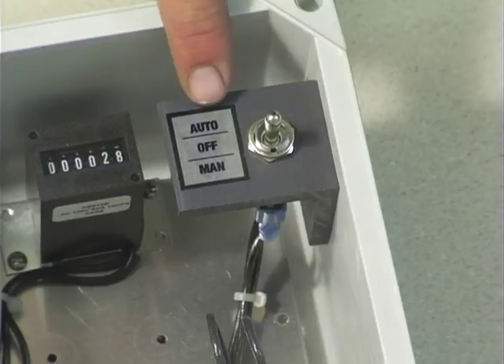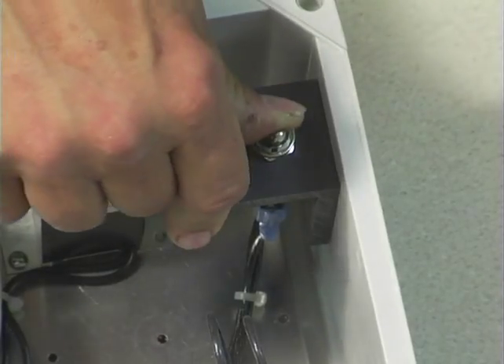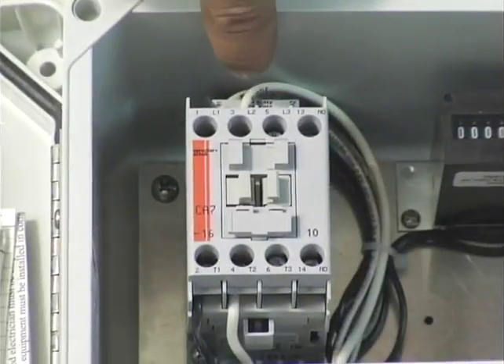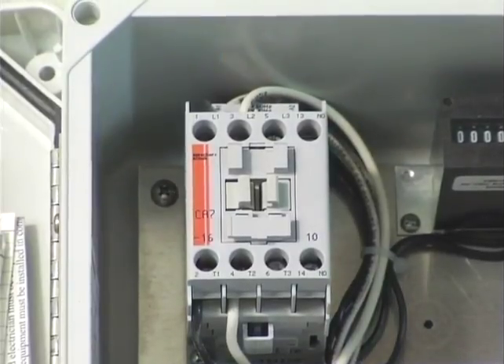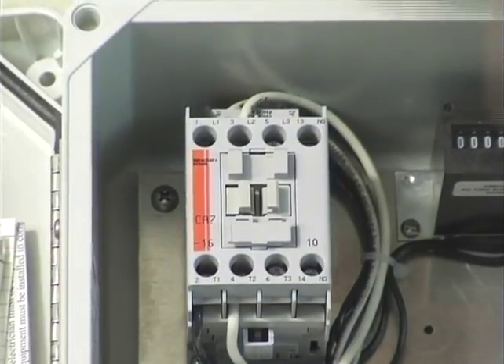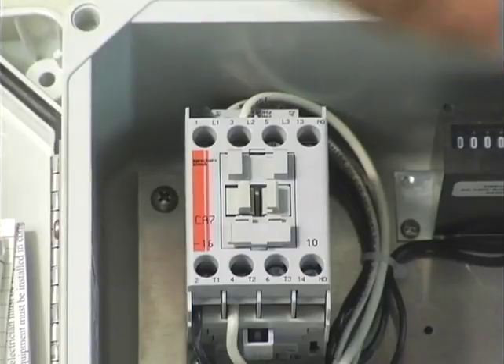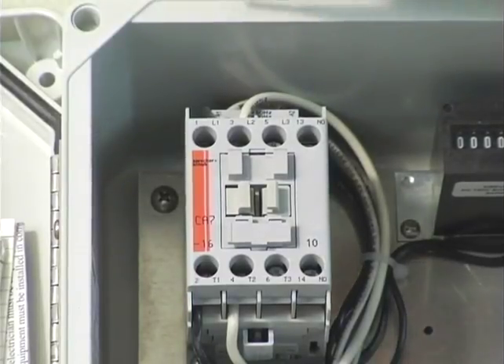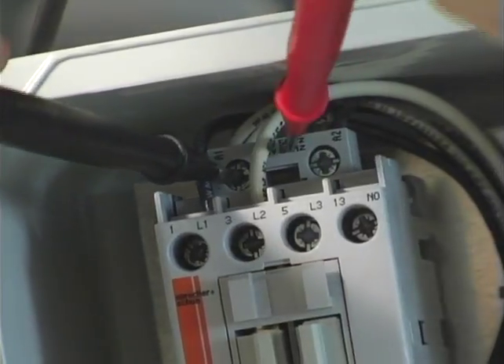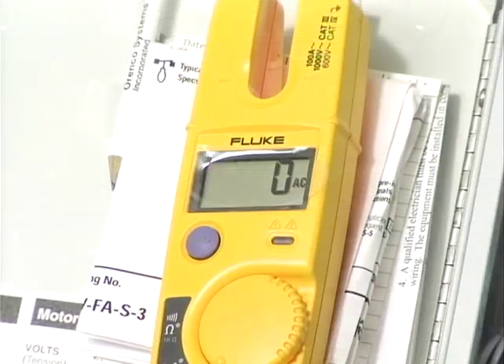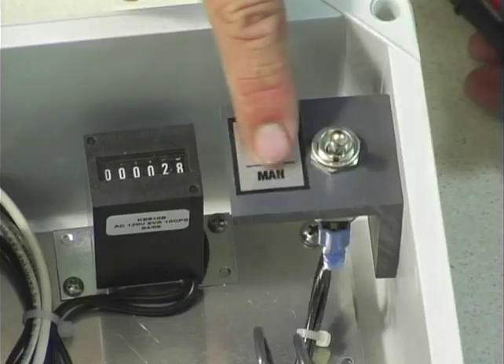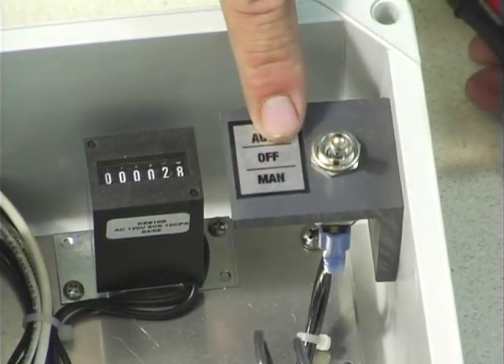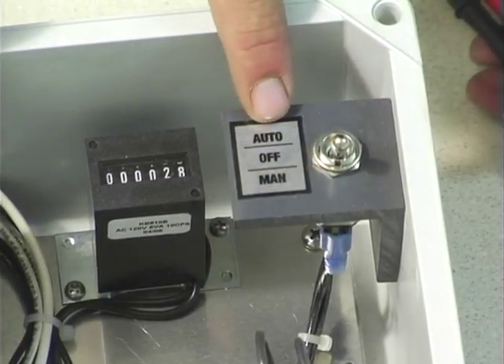What we're going to do is take our auto off manual switch, we're going to flip it into manual. Oh, our motor contactor didn't go in. So somewhere between here and here, it's not getting electricity. So what we're going to do to make sure that our motor contactor is getting power is we'll take our meters, we go to A1 and A2, and we've got no power on the meter. We've lost our electricity somewhere between the hand-off-auto switch and the motor contactor.